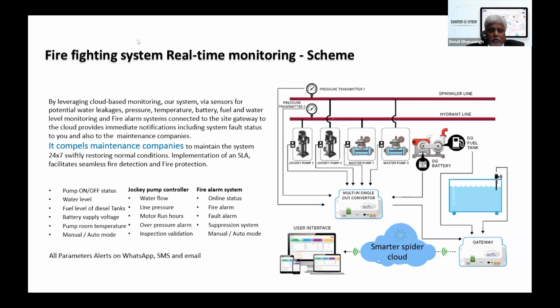It can be your laptop or your handphone, anything. So what are the parameters which we monitor from the firefighting schematic? Pump on-off status, water level, fuel level of the diesel tanks, battery supply voltage, room temperatures, auto and manual modes, water flow from the jockey pump controller, line pressure, motor run hours, overpressure, inspection validation, and fire alarm systems, the fire fault alarms on suppression system, other things. So all parameter alerts are on WhatsApp, SMS, and email. And our system compels the maintenance companies to maintain the system 24/7, swiftly restoring it to the normal condition. So implementation of an SLA facilitates seamless fire detection and protection through our smarter spider solution.